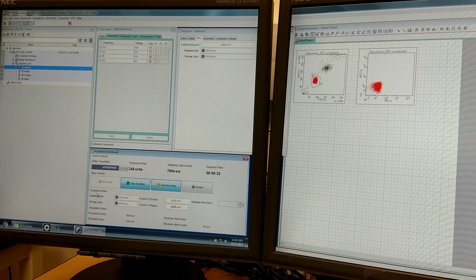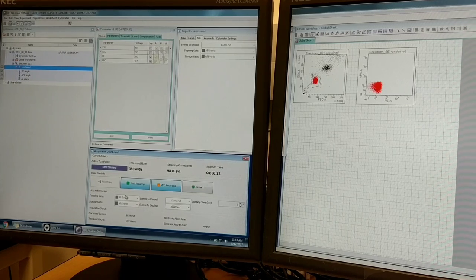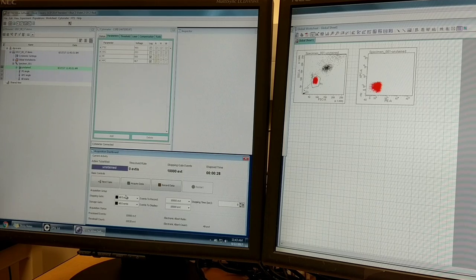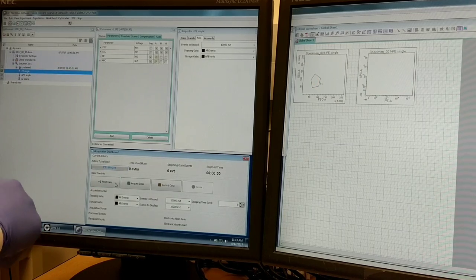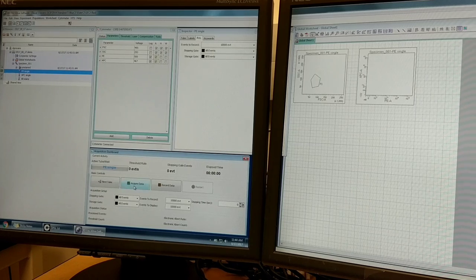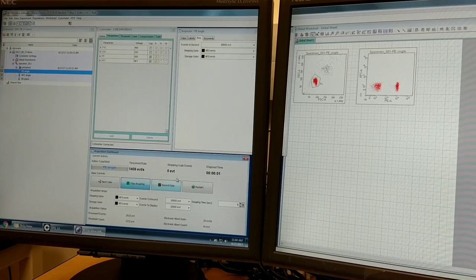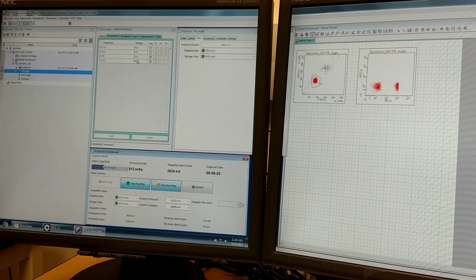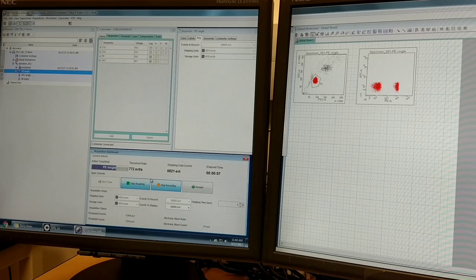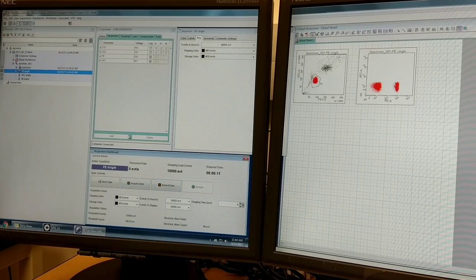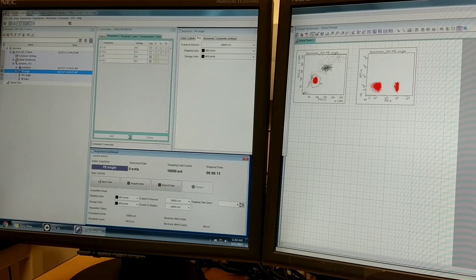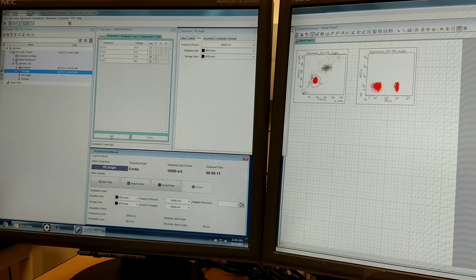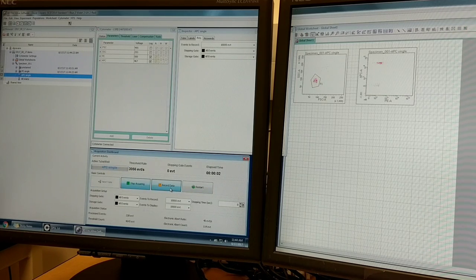There are two boxes here, one's called stopping gate and one's called storage gate. I'll come back to that in a second after I change tubes. So it's completed that one. The data appears on the screen. Now I can hit next tube. I'm going to move on to the PE single stain. If you've set it up in this way, all your values here are going to stay constant. These values will be the same from tube to tube, which is extremely important. If these voltage values are not the same from tube to tube, then you can't compare your two samples. I'm going to move on to the third sample, which is my APC single stain. It's always a good idea to record your single stains so you can fix compensation issues after the fact. I'm now recording the APC single stain.